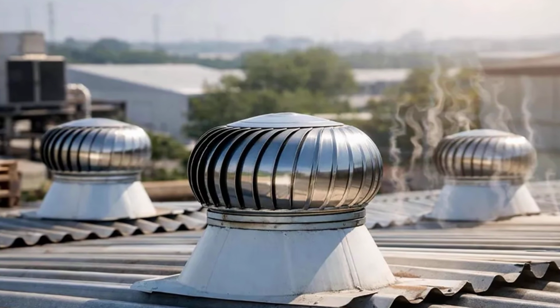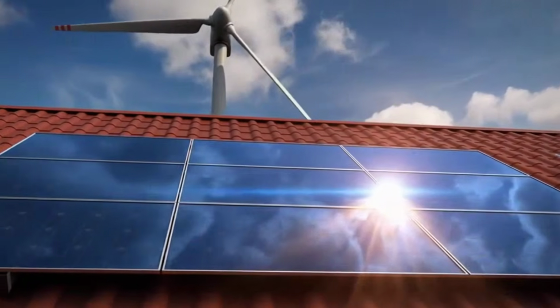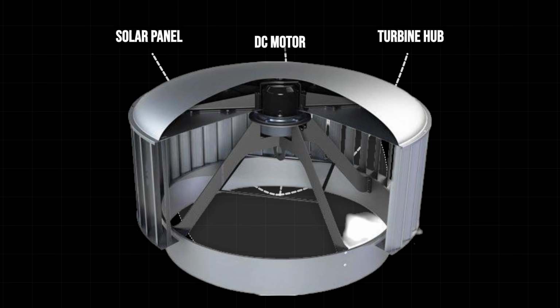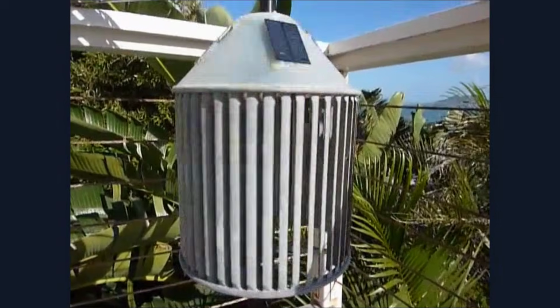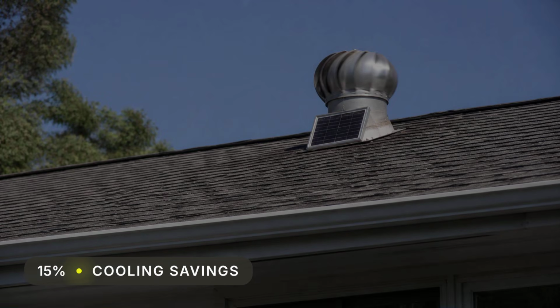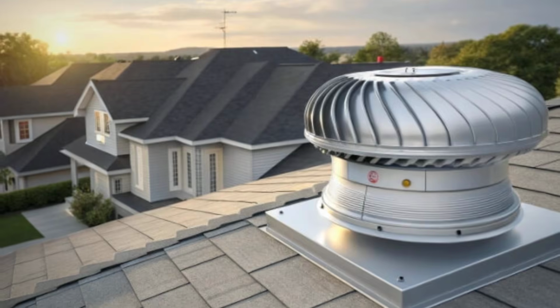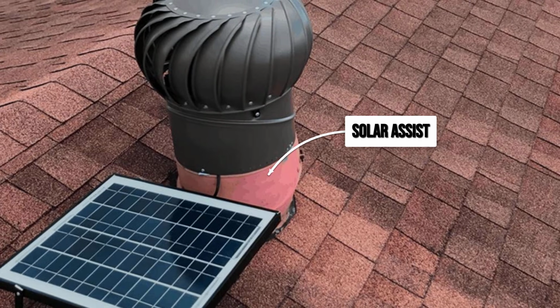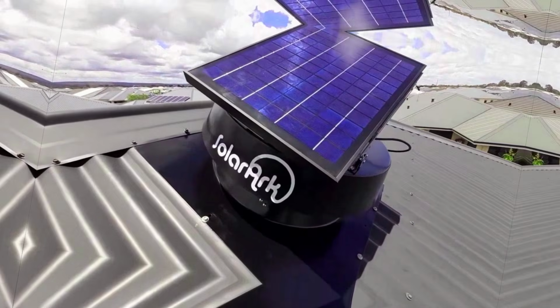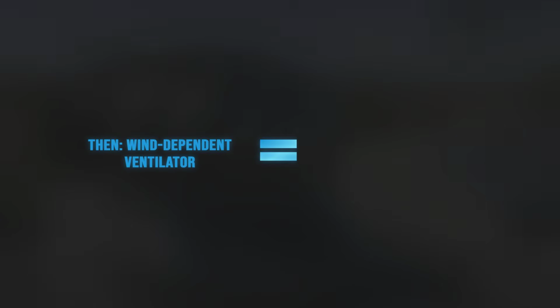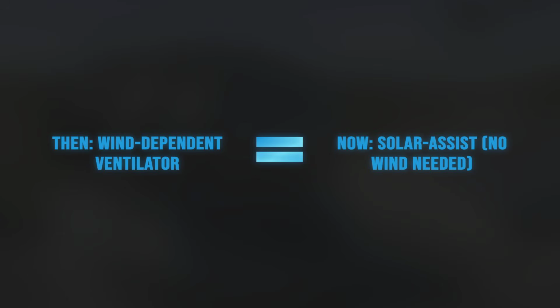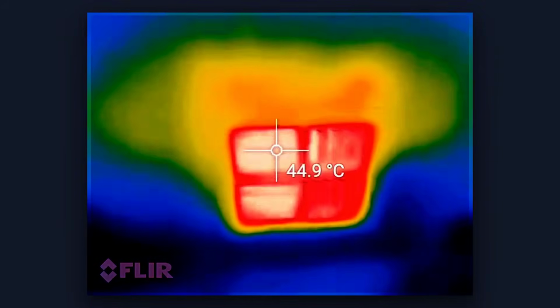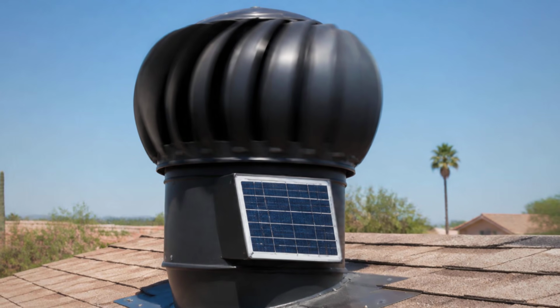The practical limitations of the turbine ventilator have also been addressed at the product level for climates where wind is inconsistent. Hybrid units now exist that combine the passive wind-driven turbine with a small solar panel that powers a supplementary motor on calm, hot days. When wind is present, the unit operates entirely passively with zero electricity consumption. When wind drops on a still summer afternoon, the solar panel provides just enough power to keep the turbine turning at minimum effective speed. These hybrid units are widely available in Australia, where the turbine ventilator never fell out of mainstream use, and are reaching mainstream distribution in the United States. The Achilles heel of the original design, its dependence on wind, has a documented engineering solution that costs roughly the same as the passive unit alone. On the hottest days of the year, the days when your air conditioning bill is at its peak, you are no longer dependent on whether the wind decides to cooperate.